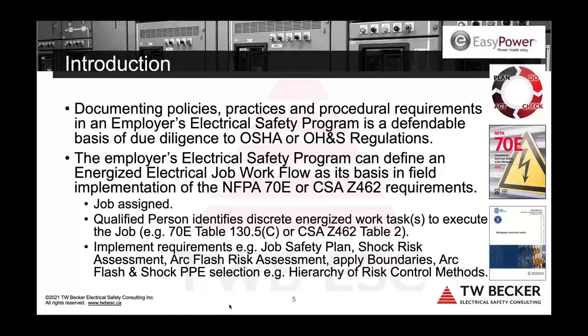So jobs are assigned. The beauty of 70E after that topic of jobs assigned is there are work task tables embedded in 70E: Table 130.5(C) in 70E and Table 2 in Z462. There are 31 work tasks. And there are tools in 70E and Z462 that the employer adapts into their electrical safety program. Then we're implementing these key or mandatory requirements. The job safety plan has to be documented. The shock risk assessment has to be documented. The arc flash risk assessment has to be documented.